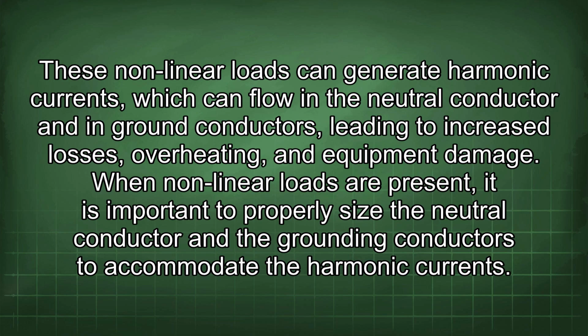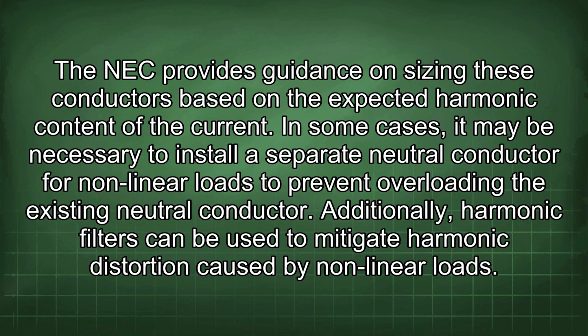When nonlinear loads are present, it is important to properly size the neutral conductor and the grounding conductors to accommodate the harmonic currents. The NEC provides guidance on sizing these conductors based on the expected harmonic content of the current. In some cases, it may be necessary to install a separate neutral conductor for nonlinear loads to prevent overloading the existing neutral conductor. Additionally, harmonic filters can be used to mitigate harmonic distortion caused by nonlinear loads.